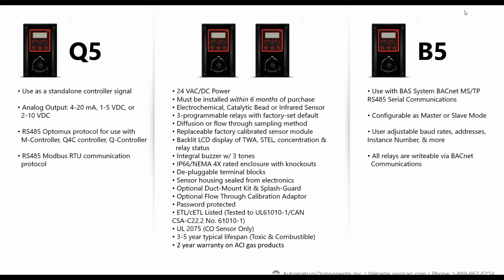It can be password protected. The COs all come with a UL 2075 certification. People always ask about the typical lifespan of a sensor, and it pretty much comes down to how concentrated the gas is in the area. If it's highly concentrated and your alarms are going off all the time, it's going to wear the sensor and you might only get 2 years. If it's more standardized, like a standard parking garage, you might get 5, 6, 7 years out of it. It all depends on the concentration of gas.